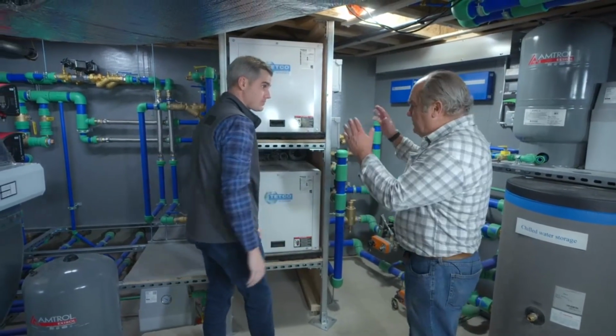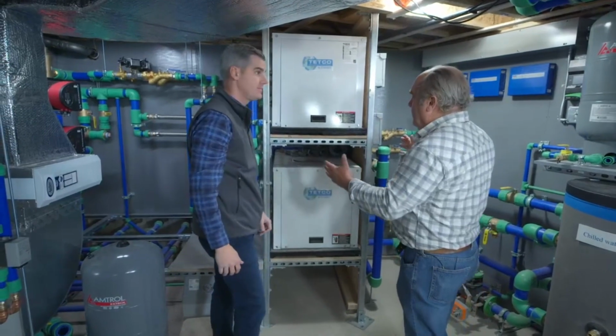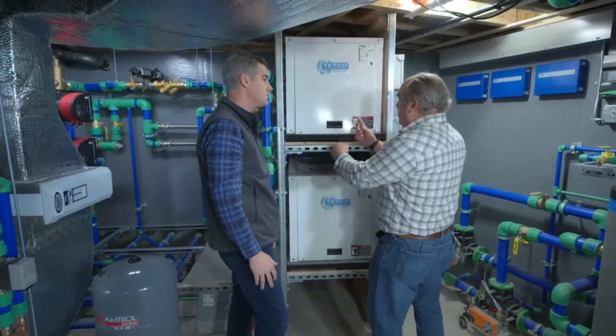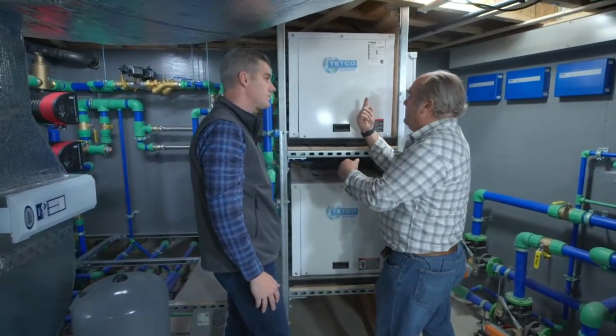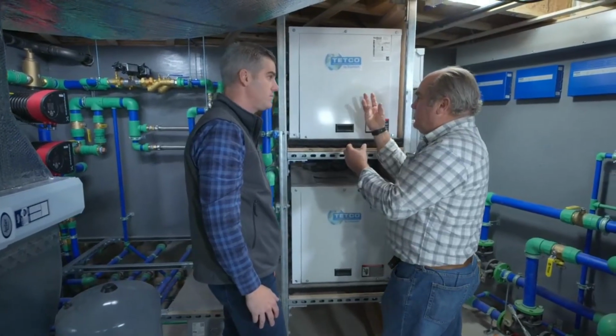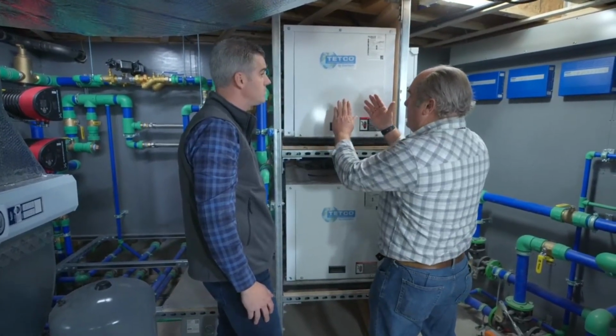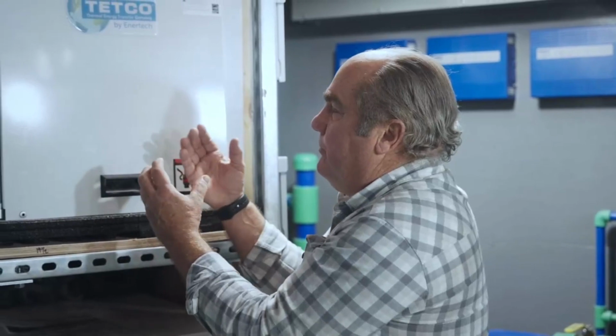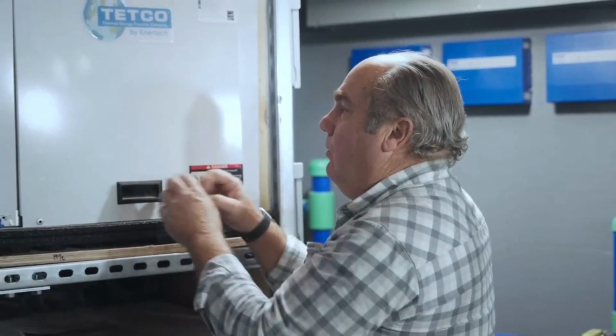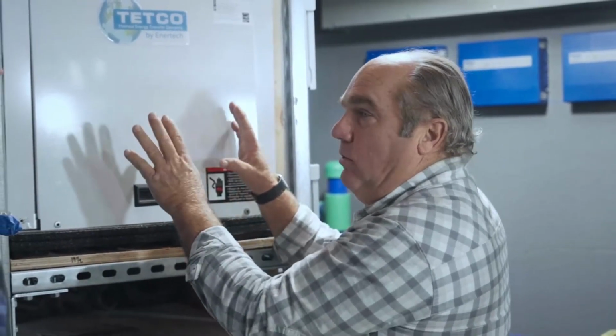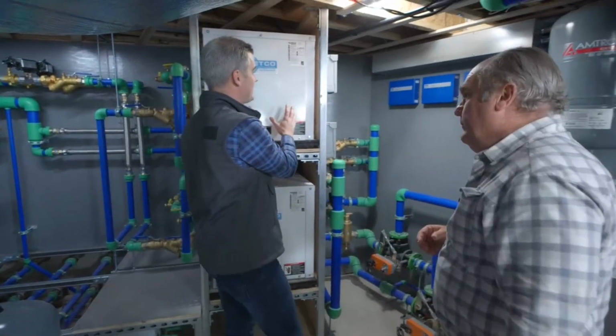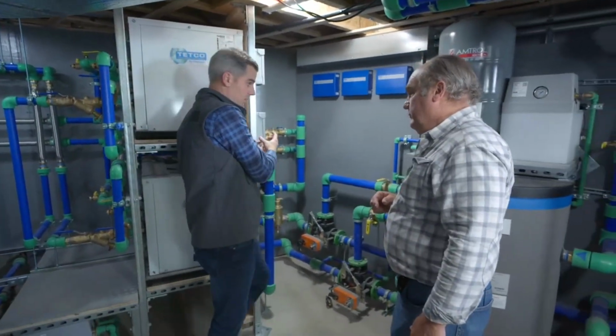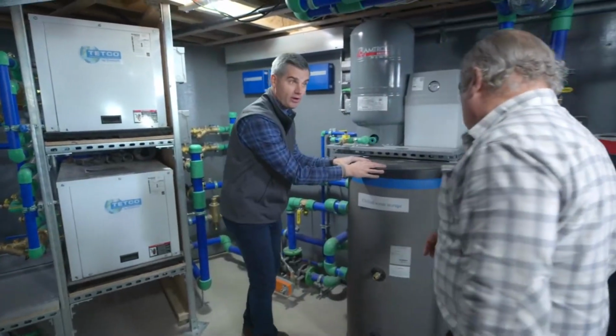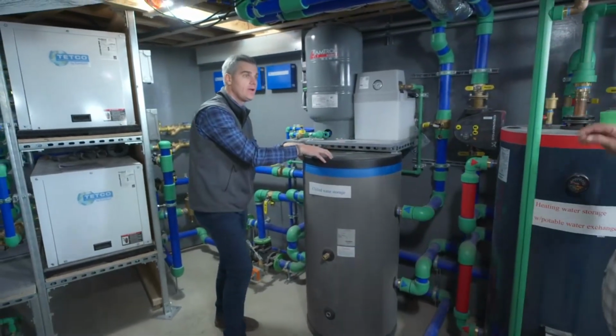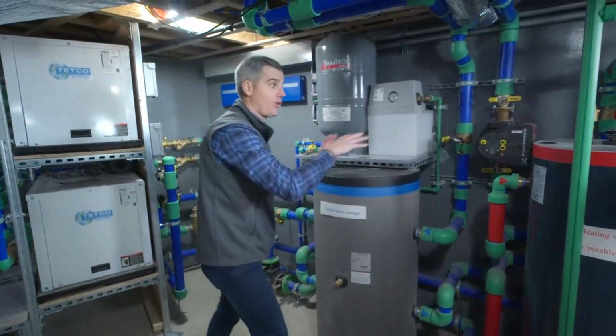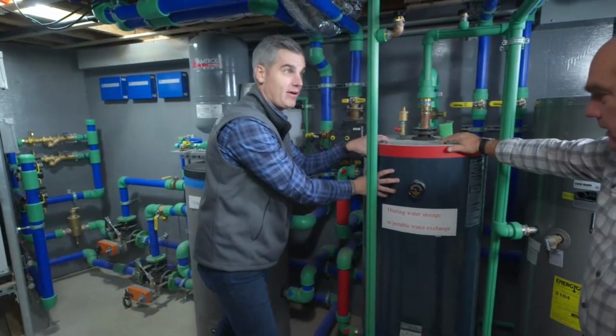Right. And these heat pumps always seem so confusing to people, but inside it's relatively simple. It's got a really efficient compressor inside that can change its speed, and you got heat exchangers inside, and that'll actually compress the refrigerant to get it hotter, or release the refrigerant to get it a little colder. That's right. And so now we can take that 45-degree water when we're cooling and store it in the chilled water tank, right? So this stores nice cold water. We can also take 120-degree water and store it in the hot tank, right, for heating the building.